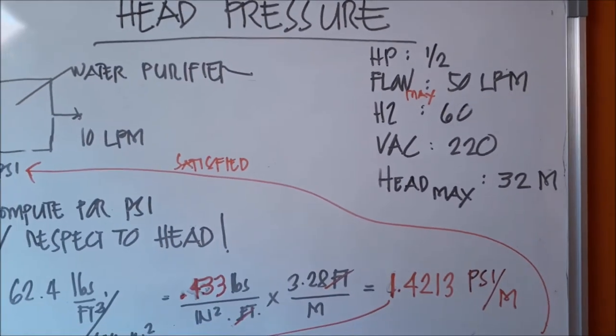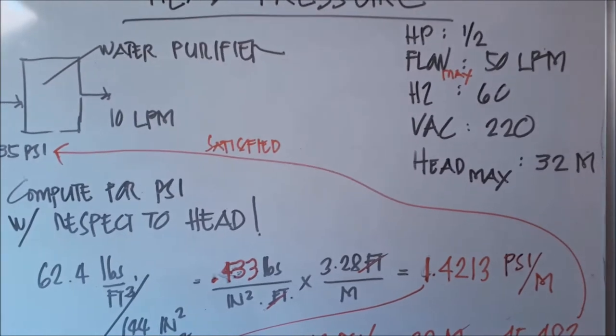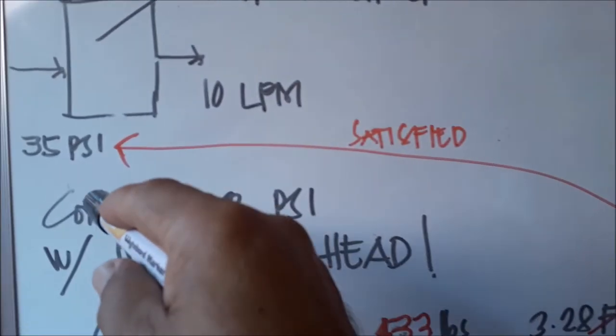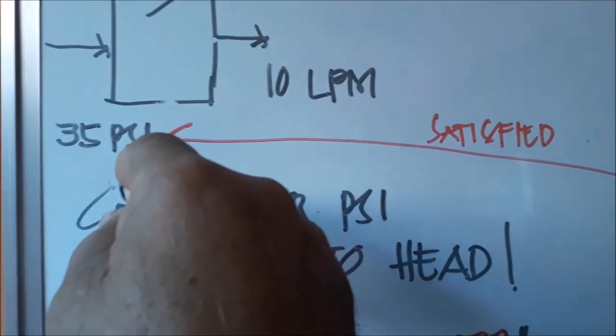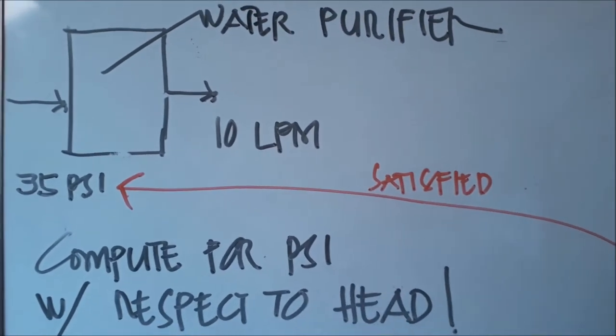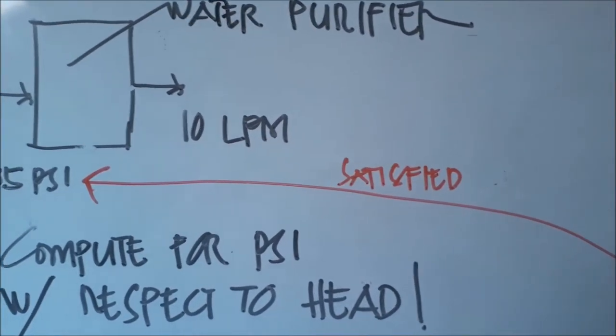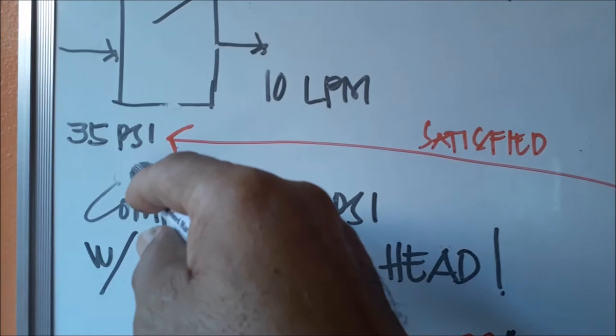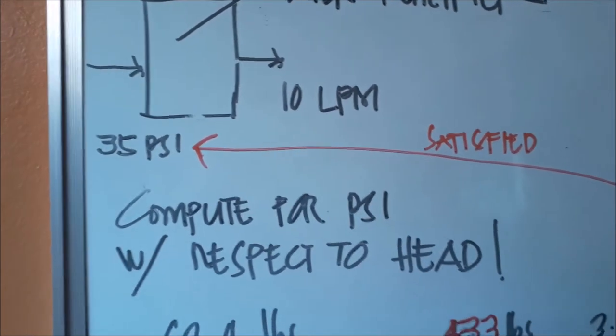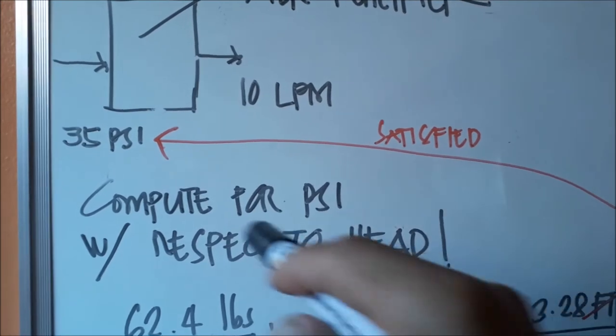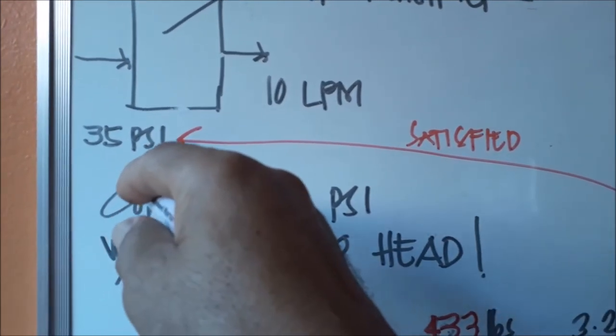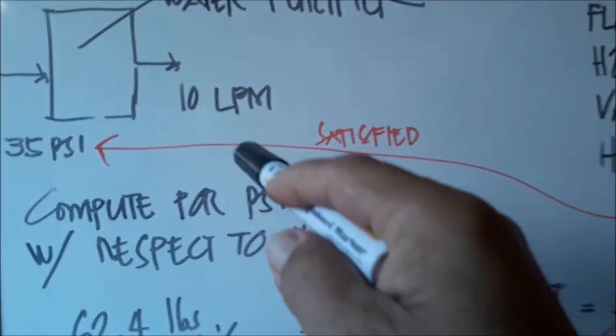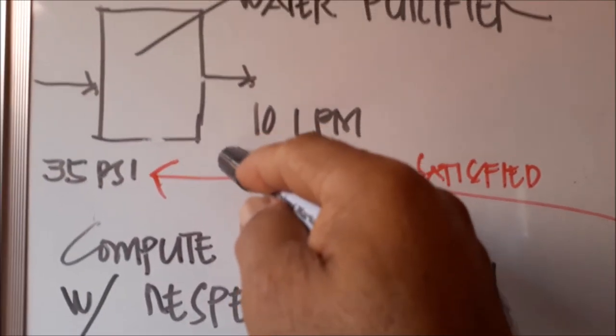We have a water purifier with a required pressure at inlet of 35 PSI. Let's find in the pump spec what can provide 35 PSI. It's okay if it's higher than 35, that's fine because the pressure can be adjusted. If you don't want it higher than 35, we can work with 40 PSI, just not below 35 because we won't meet the design flow of the water purifier.